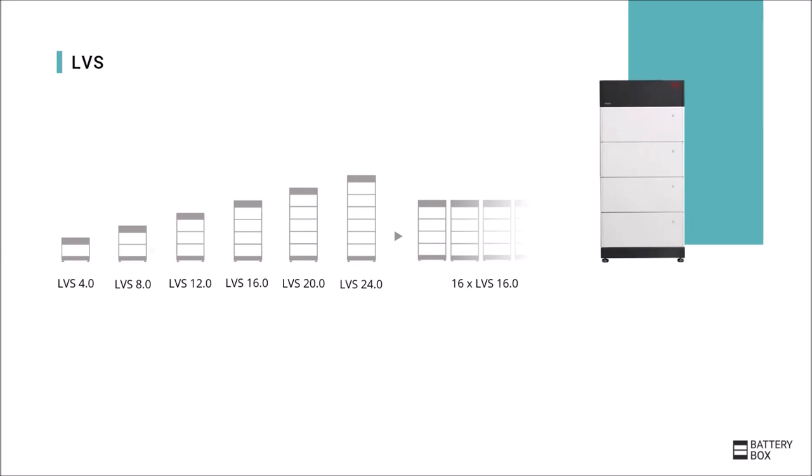One module has four kilowatt hours and you can use up to six modules in one tower, which then corresponds to 24 kilowatt hours. In addition, you can connect several LVS towers in parallel with a maximum of four modules per tower each. This way up to 256 kilowatt hours can be reached.